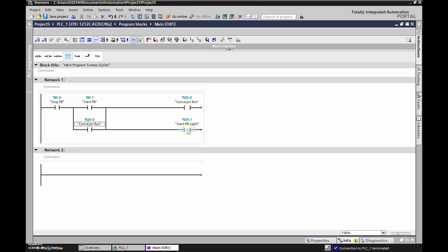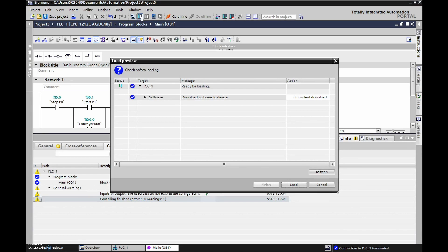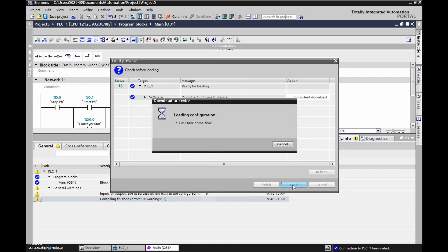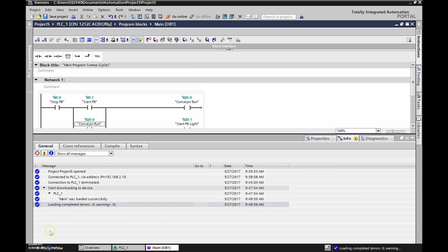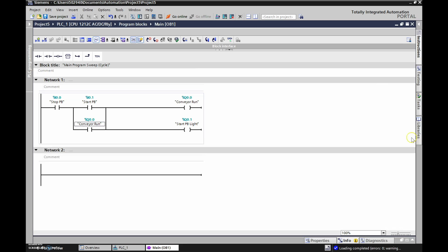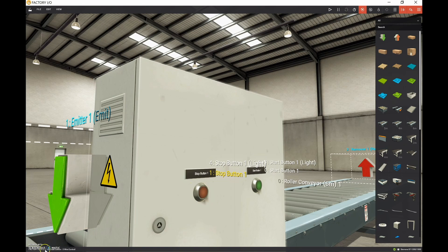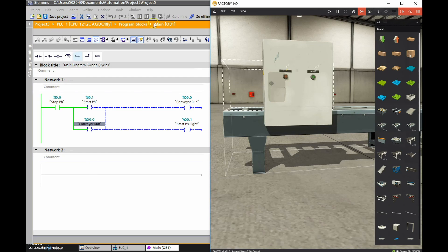Now we need to download these changes to our PLC. It's done compiling — there's one warning saying I have additional inputs that weren't there before. We're going to download to the PLC by hitting Load. Loading complete, error zero, warning zero — nice. Let's go into monitoring mode and bring up Factory IO, split the screen. We're now in monitoring mode: orange on top, green for logic continuity. Because our stop push button is already closed in Factory IO, this contact is true and it's just waiting for the start push button to be pressed.